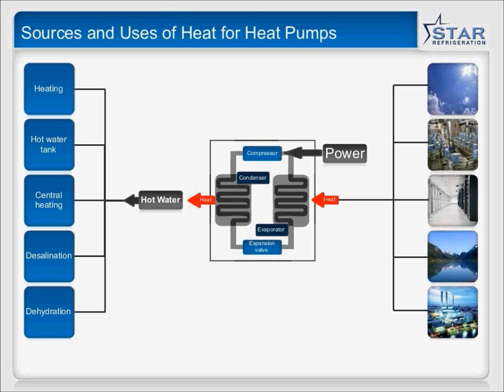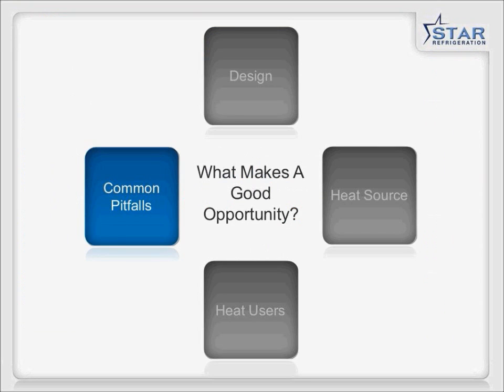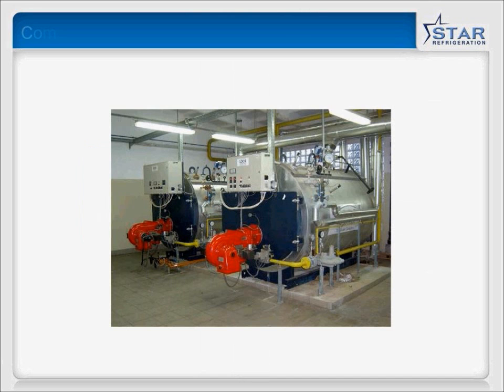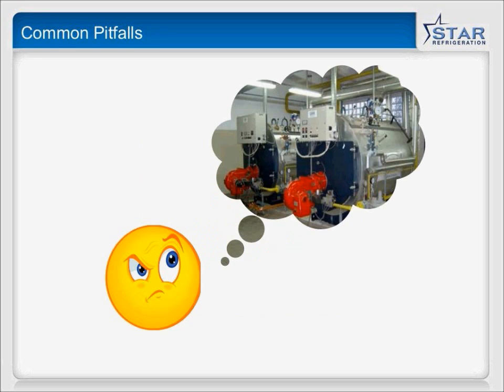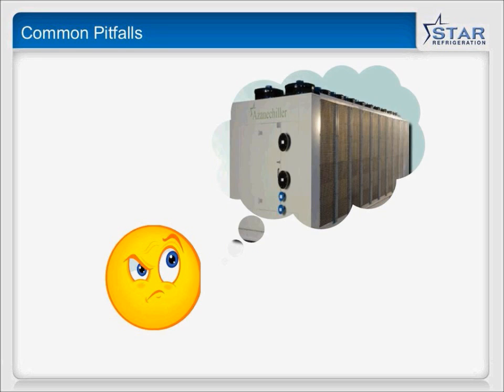Think about where energy is consumed. This does mean a bit of hard work - you've got to get in amongst it and start metering on your site. Metering hot water services is not easy, but if you don't do it, you don't know where you're actually consuming the heat. It makes no difference knowing how much your boiler is doing if you don't know where you're consuming the heat and at what temperature. In Nestle's case, they were consuming the heat at 50 degrees all around the factory. Until they measured that, they didn't know.